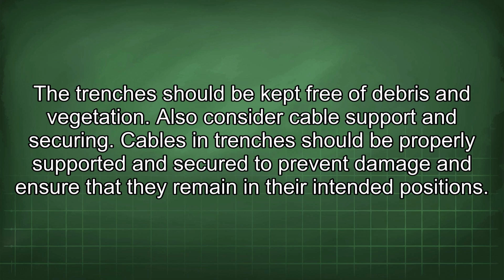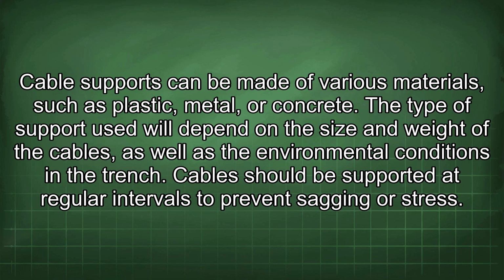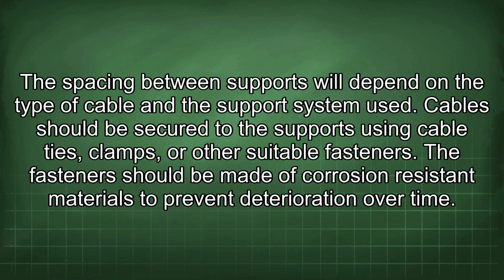Also consider cable support and securing. Cables in trenches should be properly supported and secured to prevent damage and ensure that they remain in their intended positions. Cable supports can be made of various materials, such as plastic, metal, or concrete. The type of support used will depend on the size and weight of the cables, as well as the environmental conditions in the trench. Cables should be supported at regular intervals to prevent sagging or stress. The spacing between supports will depend on the type of cable and the support system used.